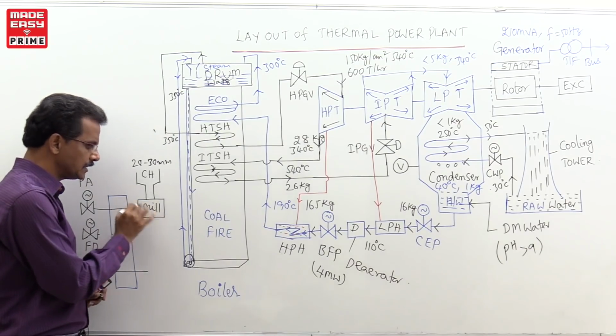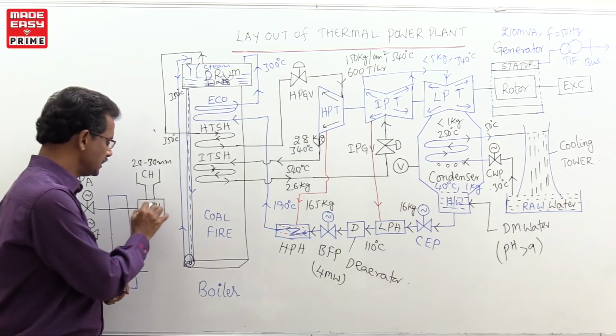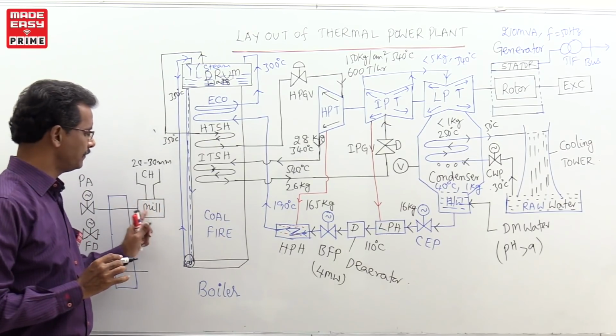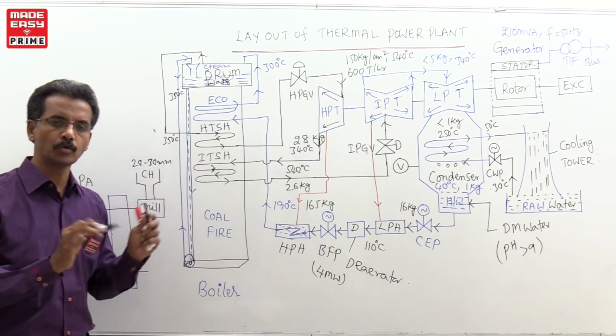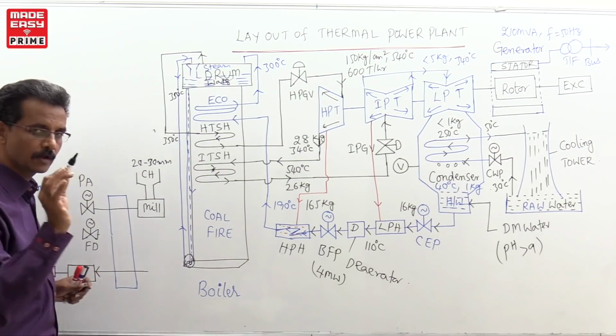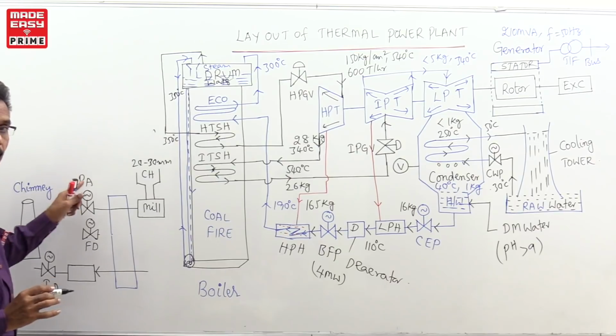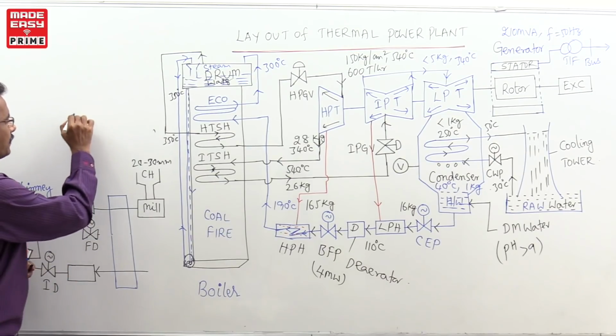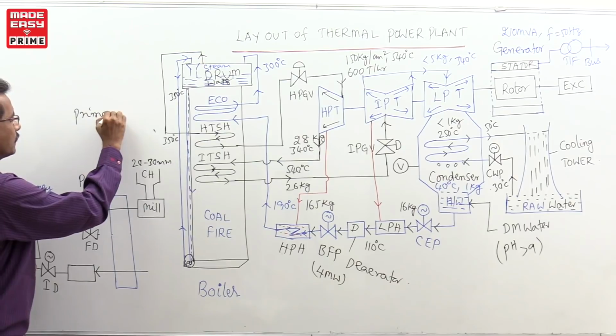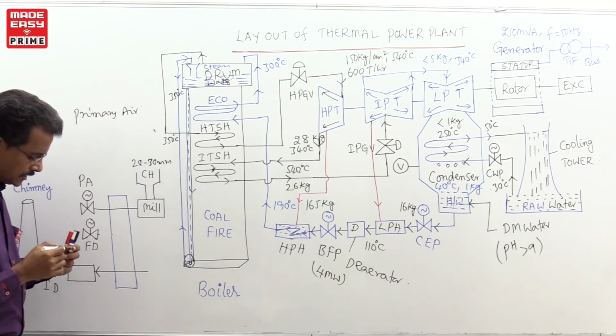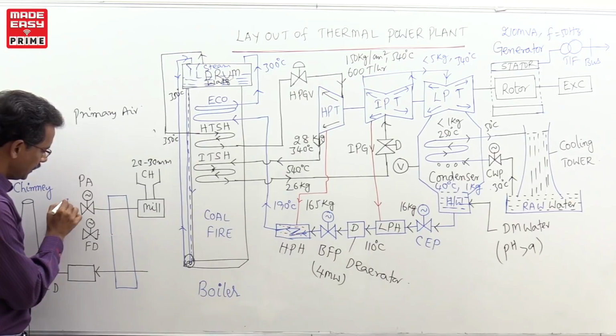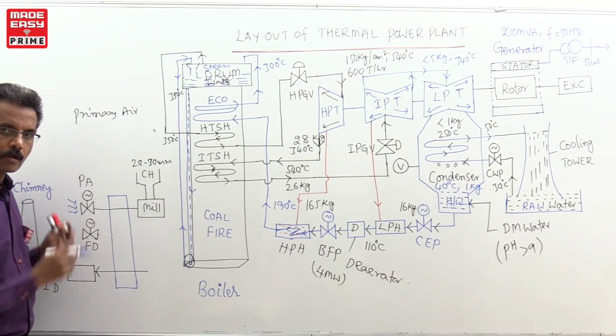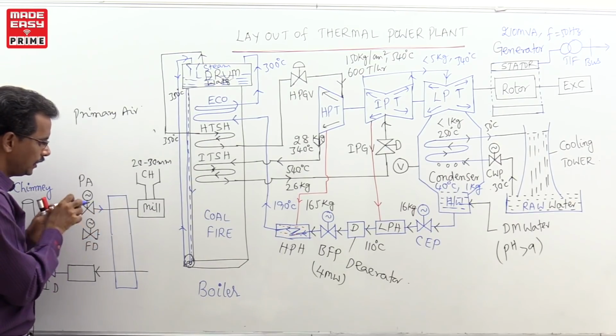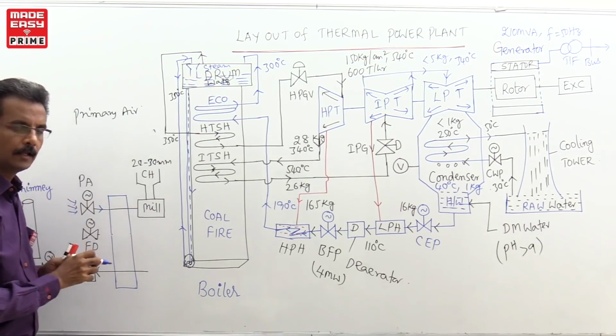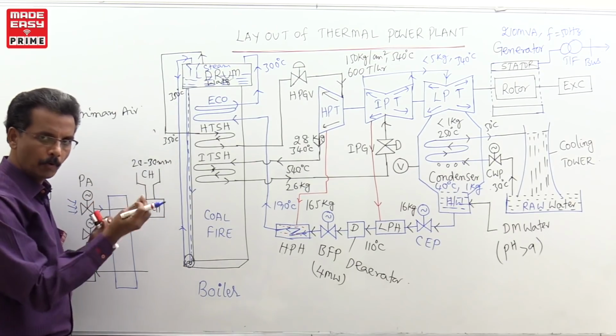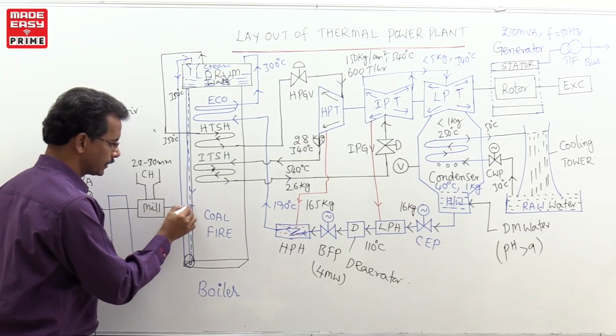Now, I want to send this coal powder from the mill to the boiler. How to send it? For this, there is one important device. This is what is called PA. PA means primary air fan. I am writing here, this is what is called primary air. This primary air fan takes the natural air from the atmosphere and sends this air inside the mill, so that it conveys the coal powder from the mill into the boiler.